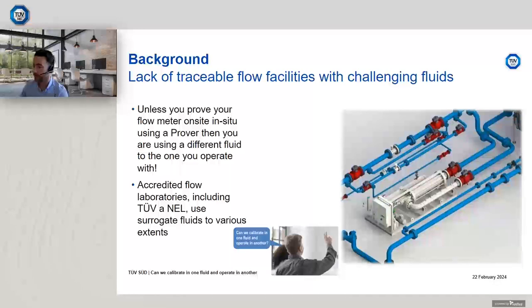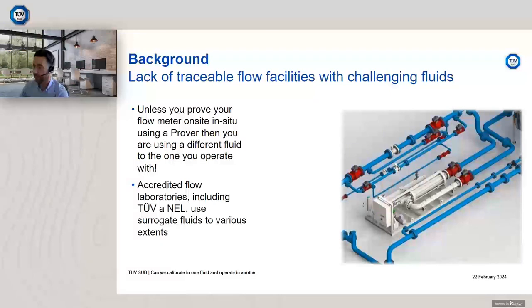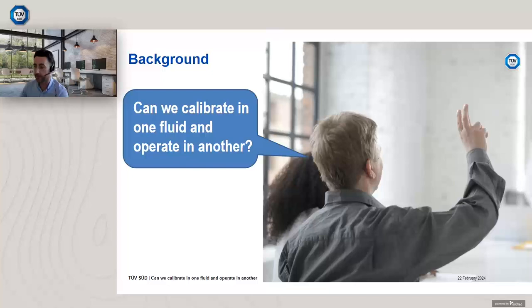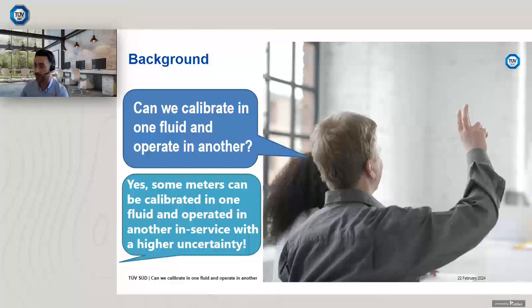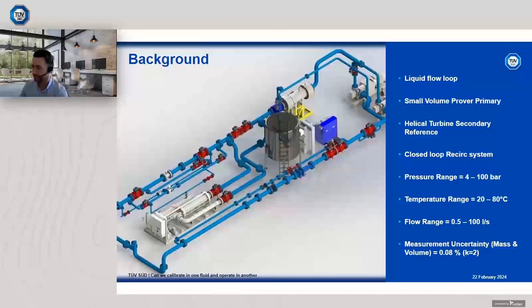So if I was answering the person from before, we go back to his question, can we calibrate in one fluid and operate in another? Well, if I was attempting to be slightly more helpful this time when he says, can we calibrate in one fluid and operate in another? Rather than say maybe, it might be better to say yes. Some meters can be calibrated in one fluid and operated in another in service, but with a higher uncertainty than you would achieve if you calibrated with that specific fluid. So a bit more detail, but again, might not fully answer the question because there's not a simple answer to that question.